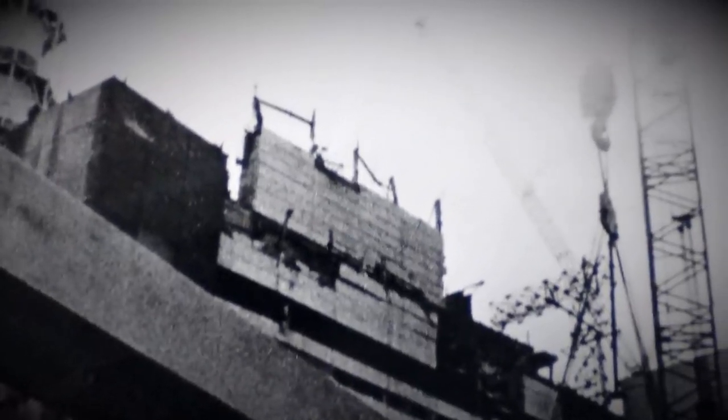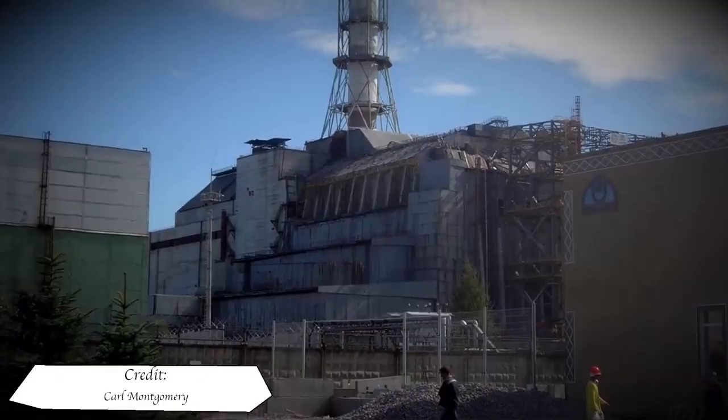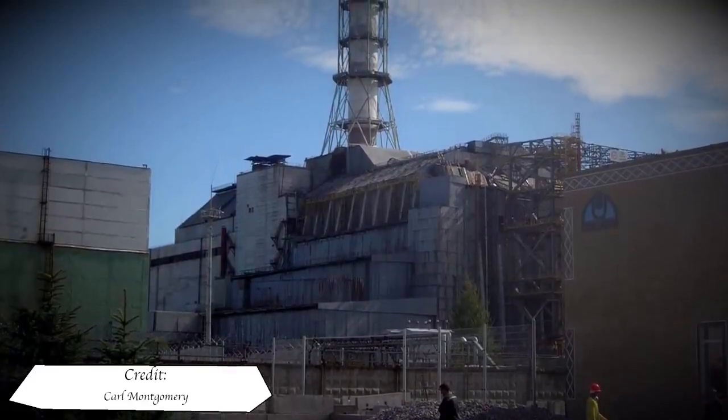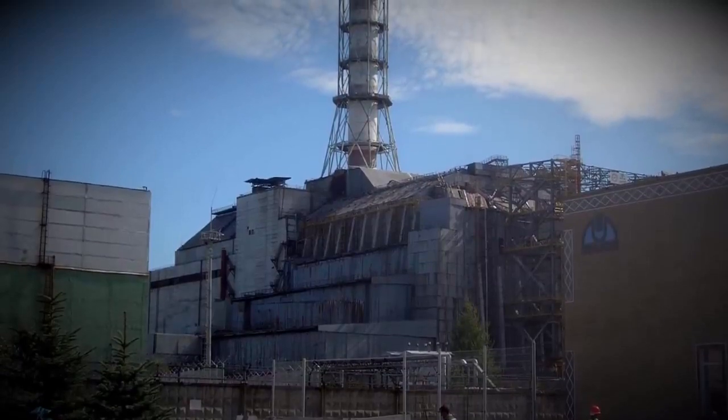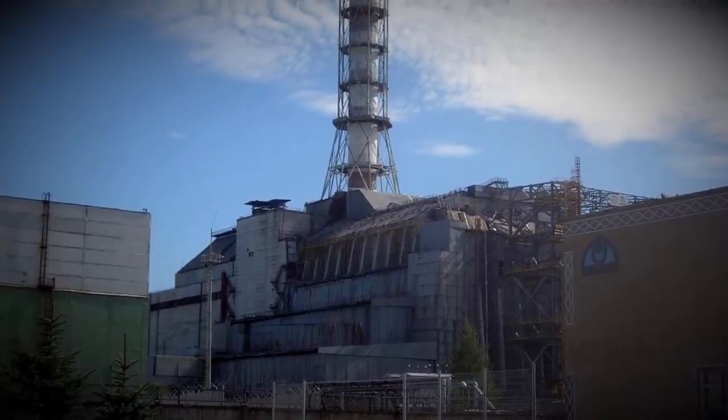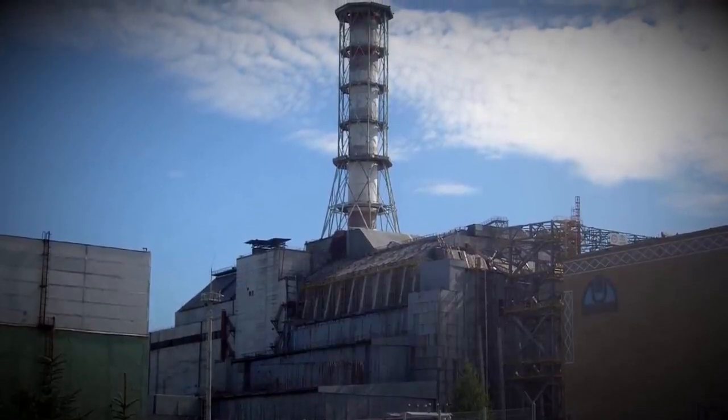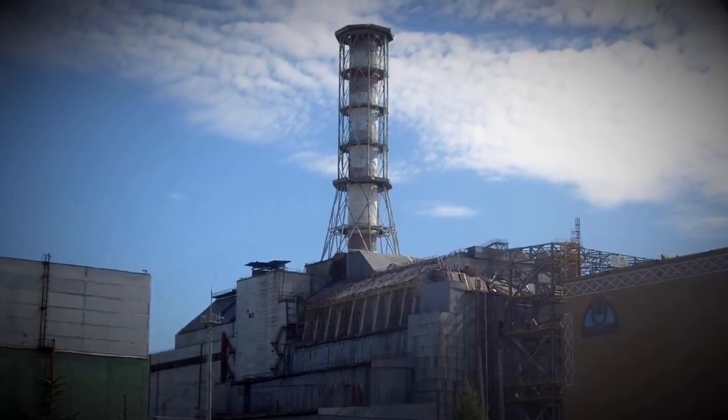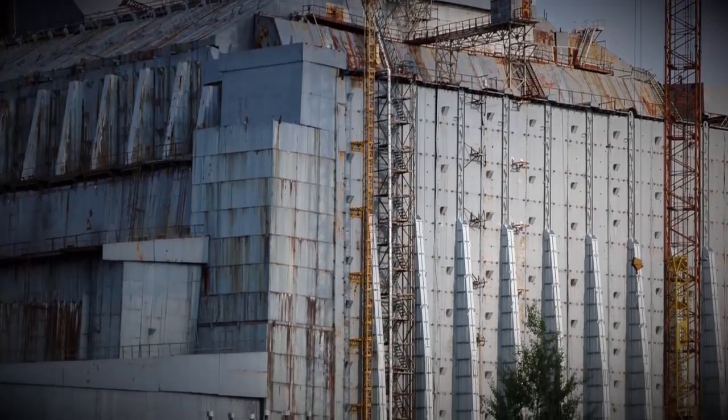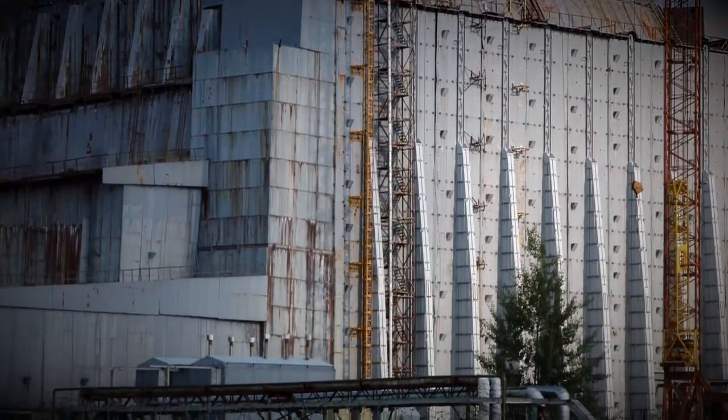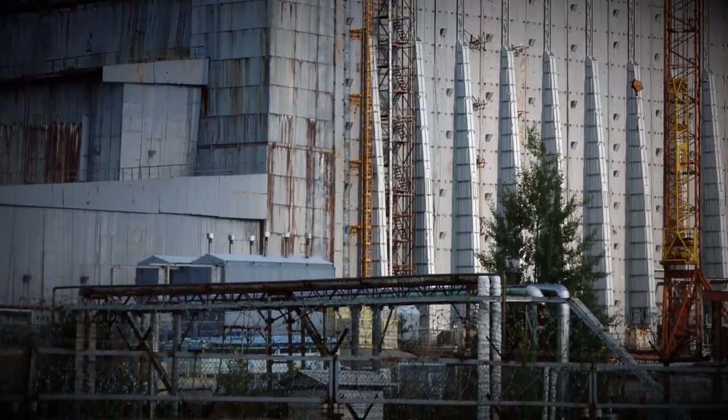The construction was undertaken over eight stages, all whilst unit 4 released contamination and next to unit 3, which still needed to be operable. Concrete containment walls were built around unit 4, and dividing walls erected between it and unit 3. The sarcophagus was placed on top of the concrete containment walls. More than 400,000 cubic meters of concrete and 7,300 tons of metal were used during the construction. The building encapsulated an estimated 740,000 cubic meters of heavily contaminated debris together with contaminated soil. Holes were installed in the structure to allow pressure release, albeit through a filtration system. The shelf life of the structure was only thought to be around 20 to 30 years, necessitating a new containment structure, but this will probably be covered in the next video in this series.